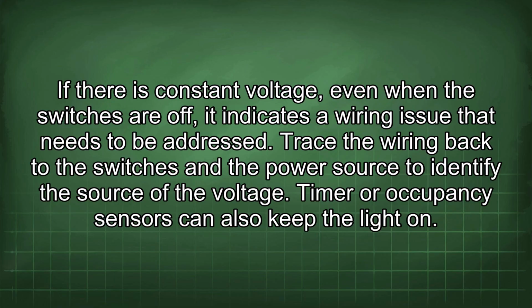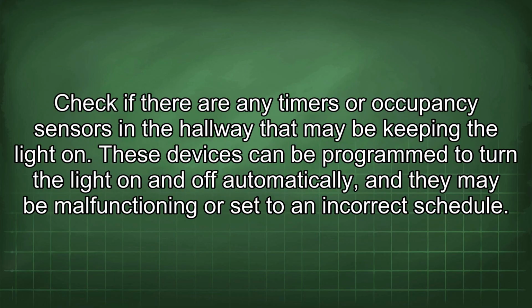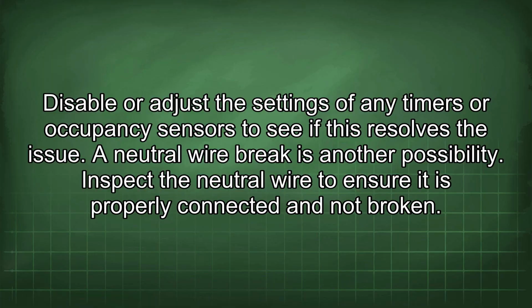Timer or occupancy sensors can also keep the light on. Check if there are any timers or occupancy sensors in the hallway that may be keeping the light on. These devices can be programmed to turn the light on and off automatically, and they may be malfunctioning or set to an incorrect schedule. Disable or adjust the settings of any timers or occupancy sensors to see if this resolves the issue. A neutral wire break is another possibility.